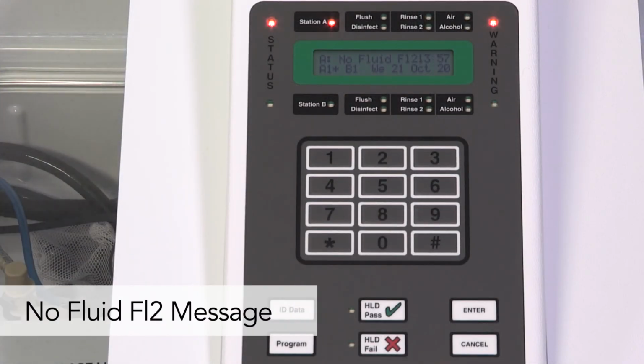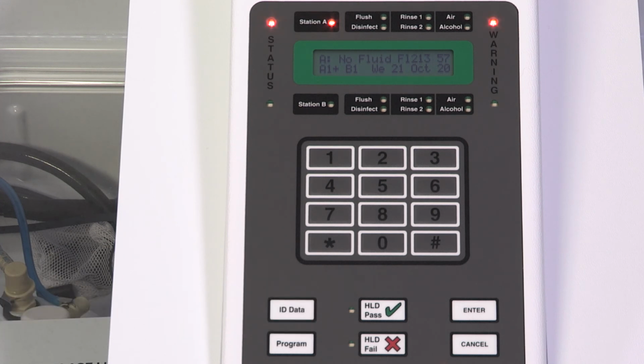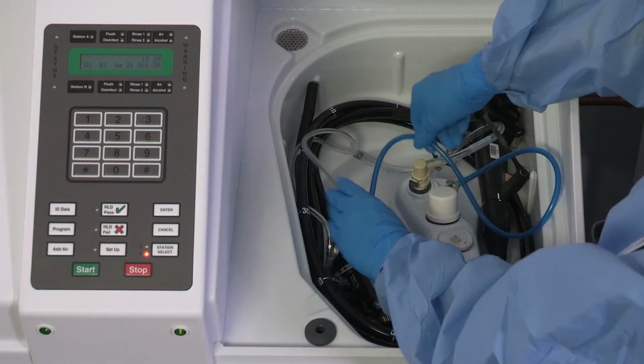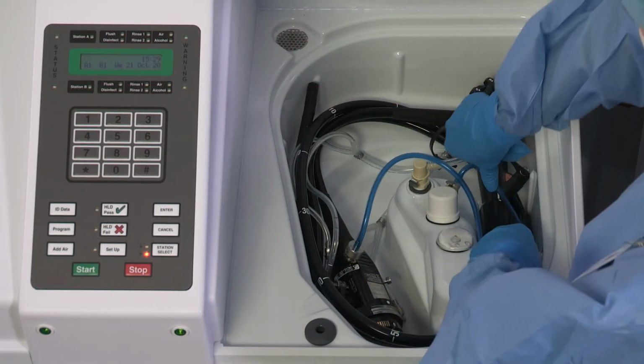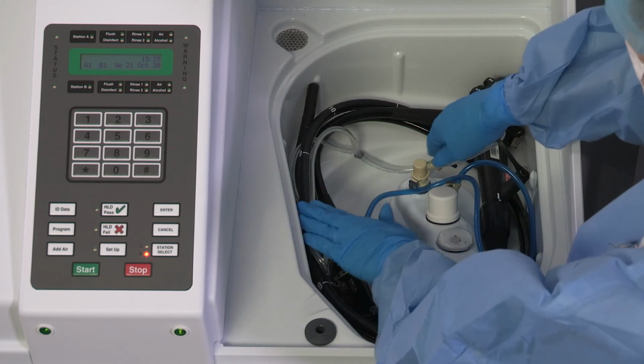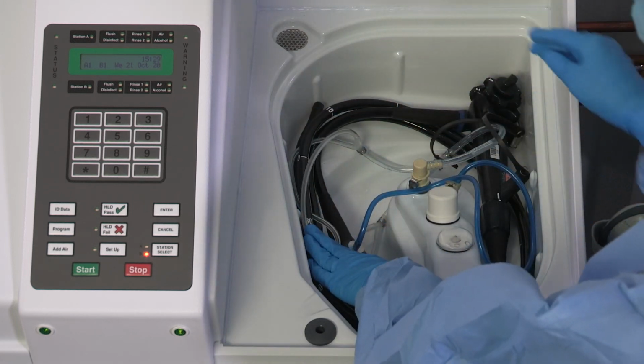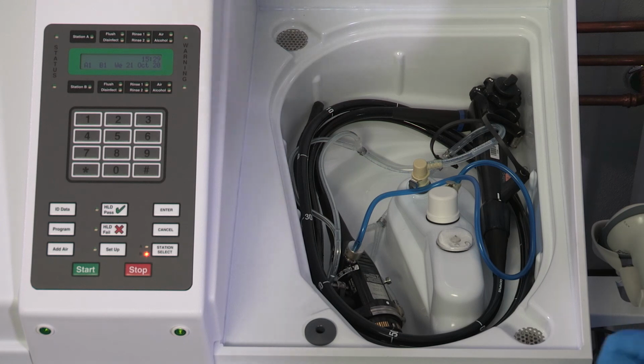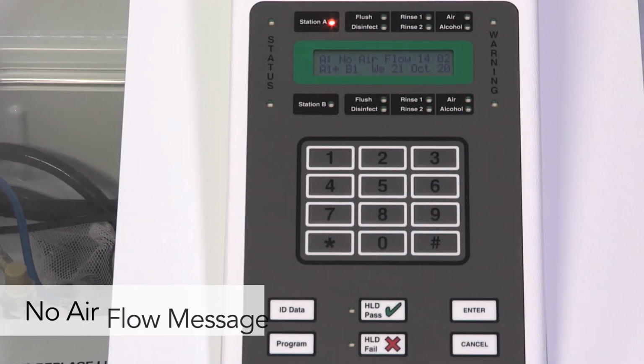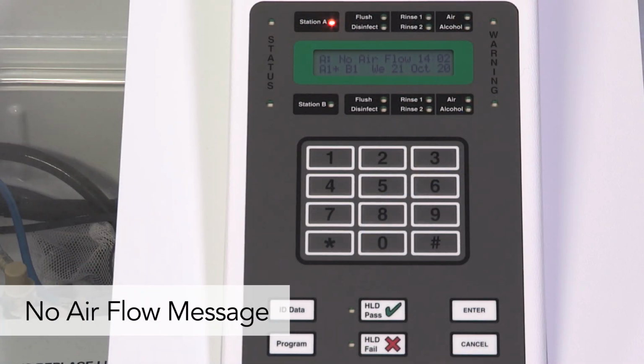A no fluid Fl2 error indicates no disinfectant was flowing to the basin. This error can only occur during the disinfectant stage of the cycle. Examine the basin drain for objects that are causing the blockage. For example, a mesh bag covering or a reusable button stuck in the drain. A no airflow message indicates no air is detected or flowing. Consider replacing the air filter.